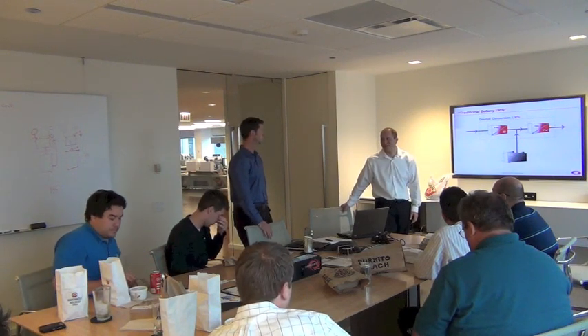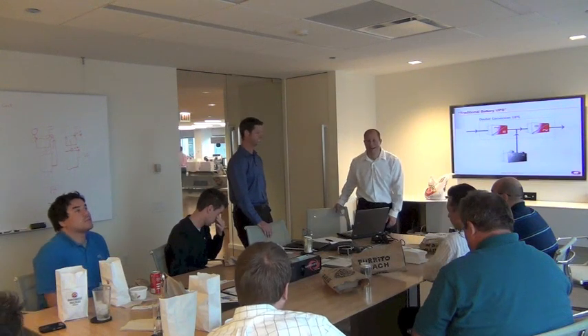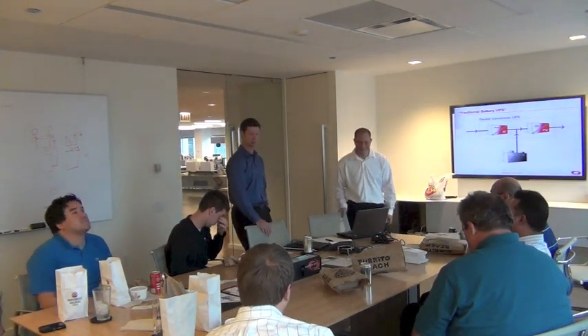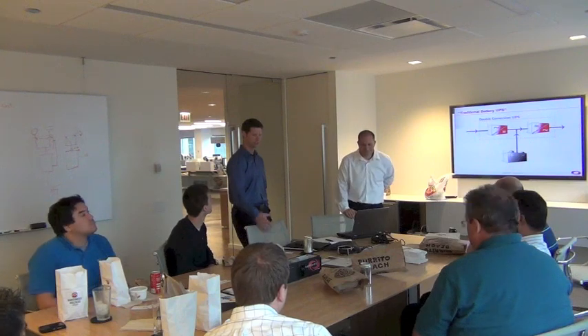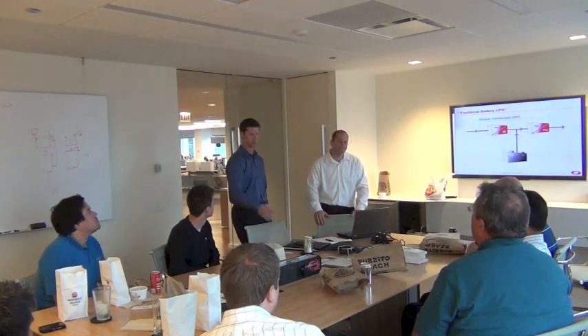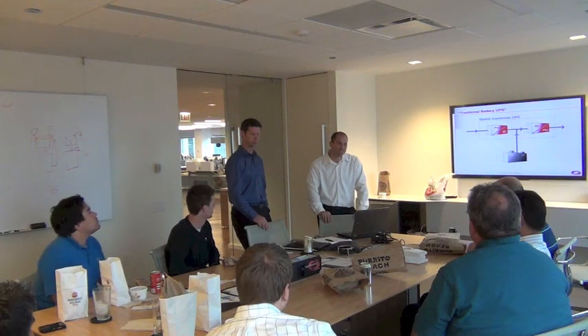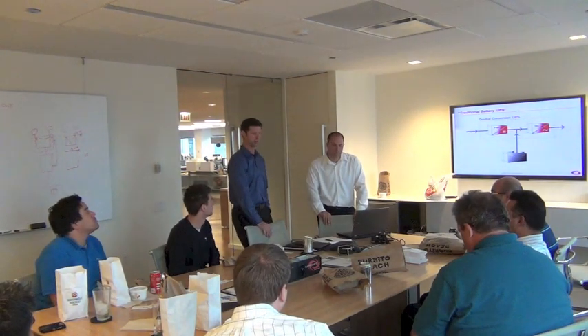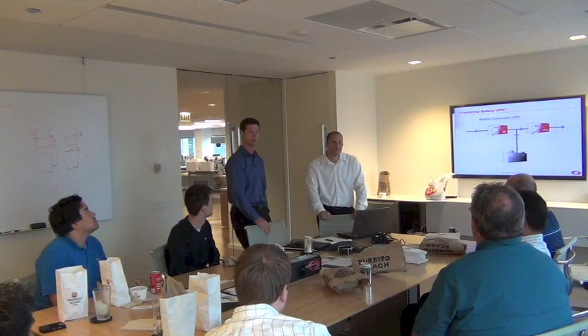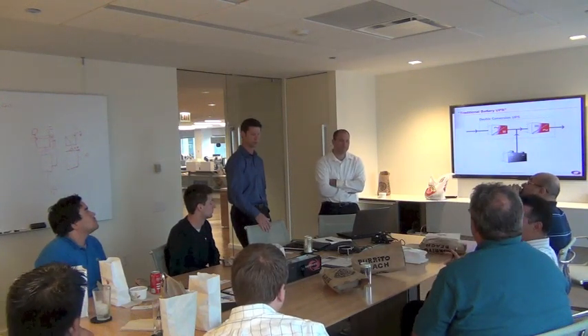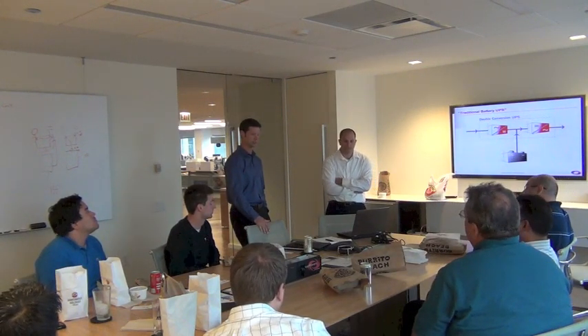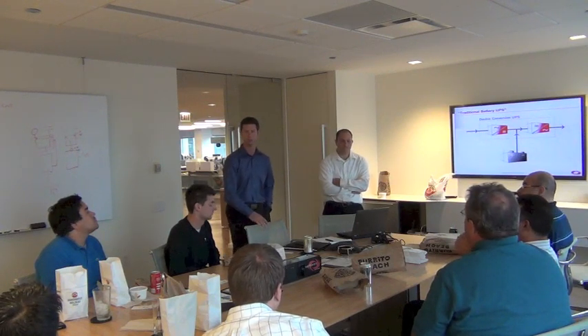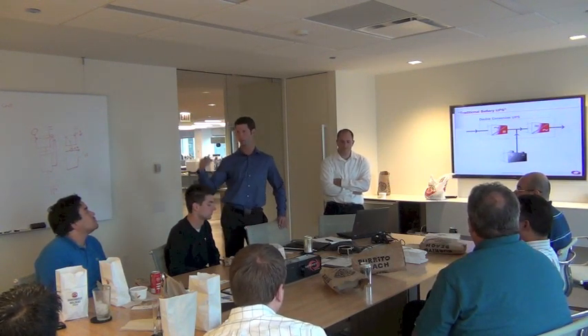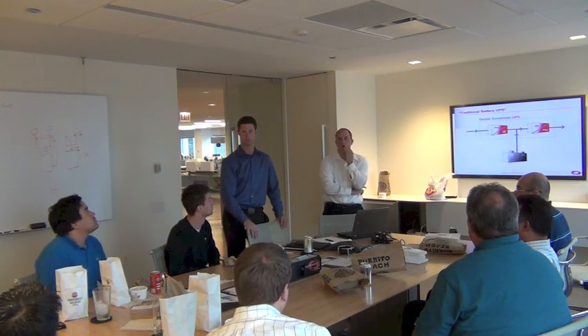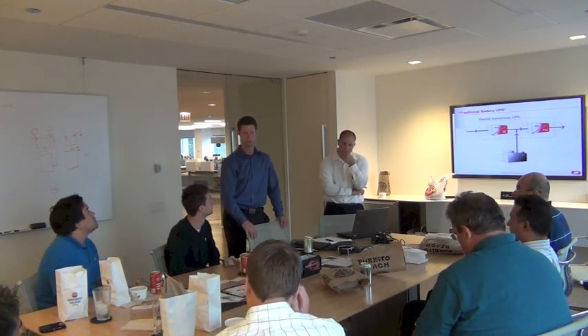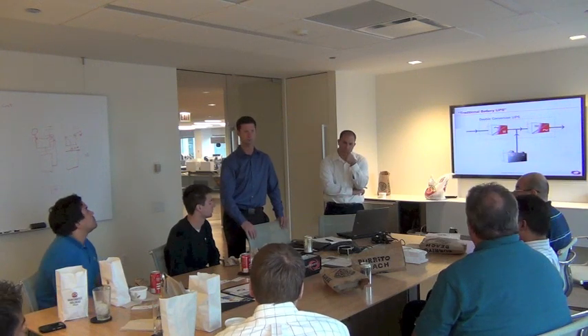You have interest across the east and west. I don't want to get into negative selling; I can only do that internally. I spent 5 years at APC selling APC MGE. We respect them. There are applications for flywheel and applications for batteries, and sometimes you could look at one or the other. Obviously, we're not going to tell you to use a flywheel for every system, but hopefully you recognize the inherent value in the space savings and carbon footprint savings, and in the fact that you can design a very reliable system around flywheel based on the parameters we give it, which helps you engineer it, and we support you on that. APC, Mitsubishi, Toshiba, they're all good companies. We all have our pros and cons, and ups and downs, right?